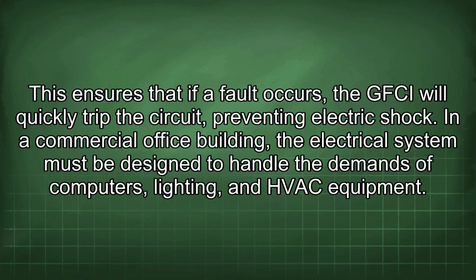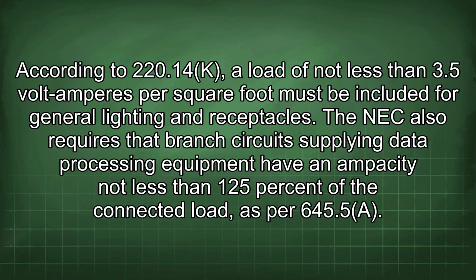In a commercial office building, the electrical system must be designed to handle the demands of computers, lighting, and HVAC equipment. According to 220.14(K), a load of not less than 3.5 volt-amperes per square foot must be included for general lighting and receptacles.